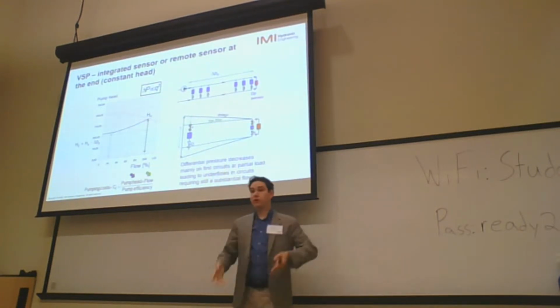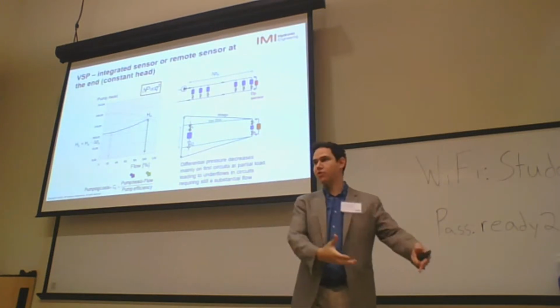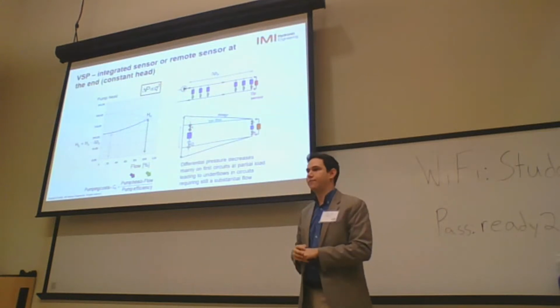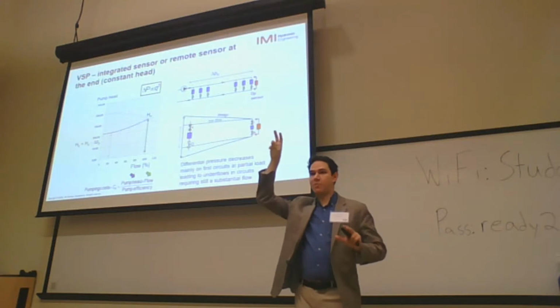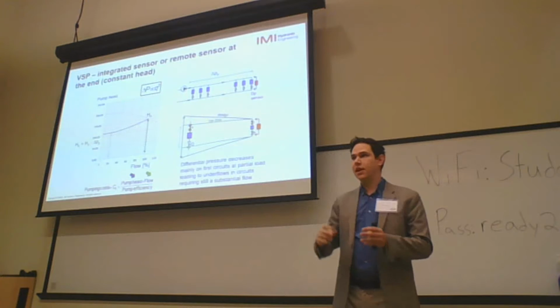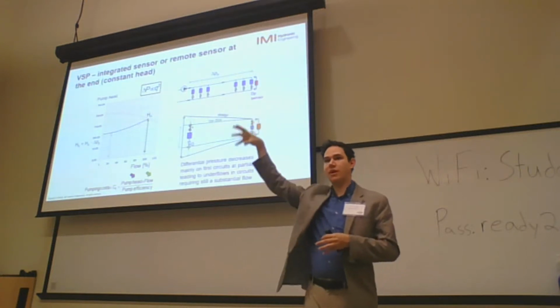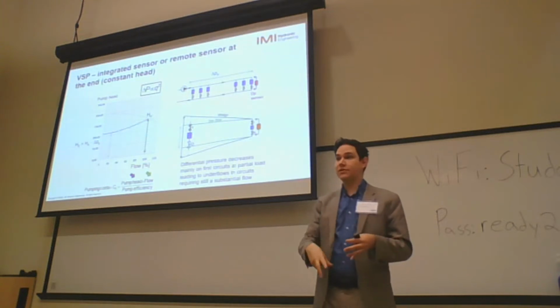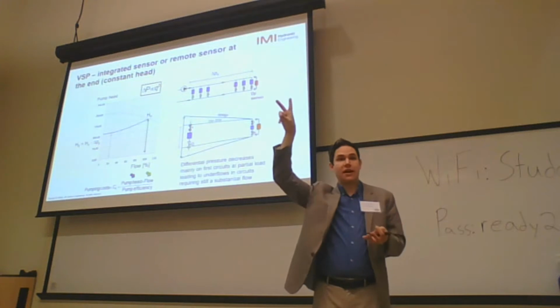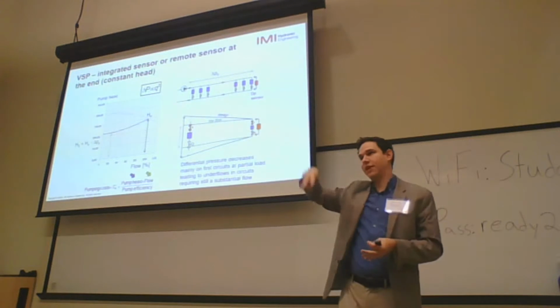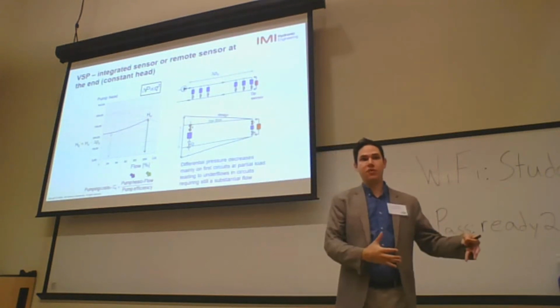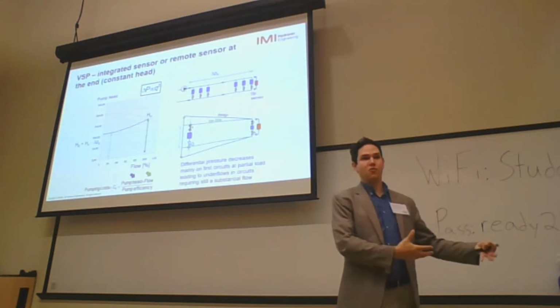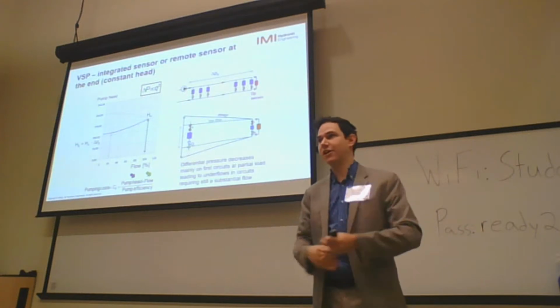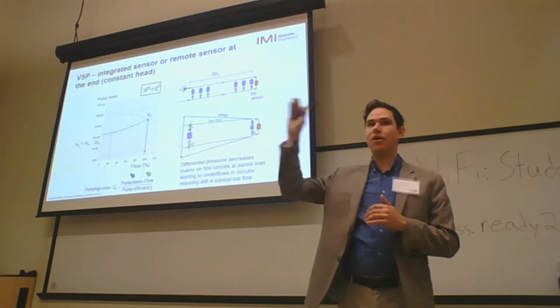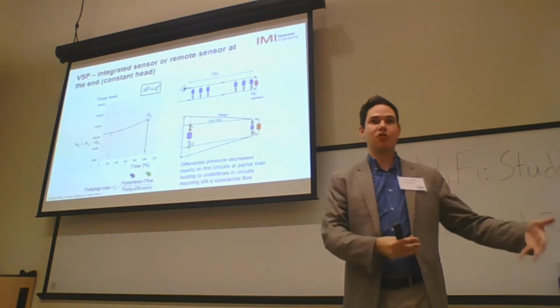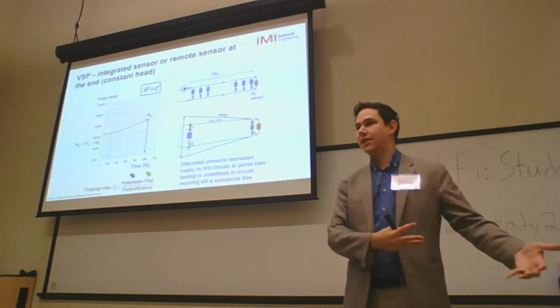A good example of this one is to think about a hotel, where you have the conference room on the first floor and many hotel rooms in the tower. My DP sensor is right there at the last floor, and my mechanical room is on the first floor. What's going on is, during business hours nobody's in the hotel rooms, everybody's at the conference room at the bottom. So at my index coil it is a low flow, low capacity in my whole system, so it's only getting the minimum flow for the whole tower. But in my conference room, where I have a lot of people and a high load, I may not get enough water just because of the load in this example. So basically my whole system is running at a lower capacity, and my conference room is where I needed the highest load. The control valve is fully open, asking for water and not getting enough.